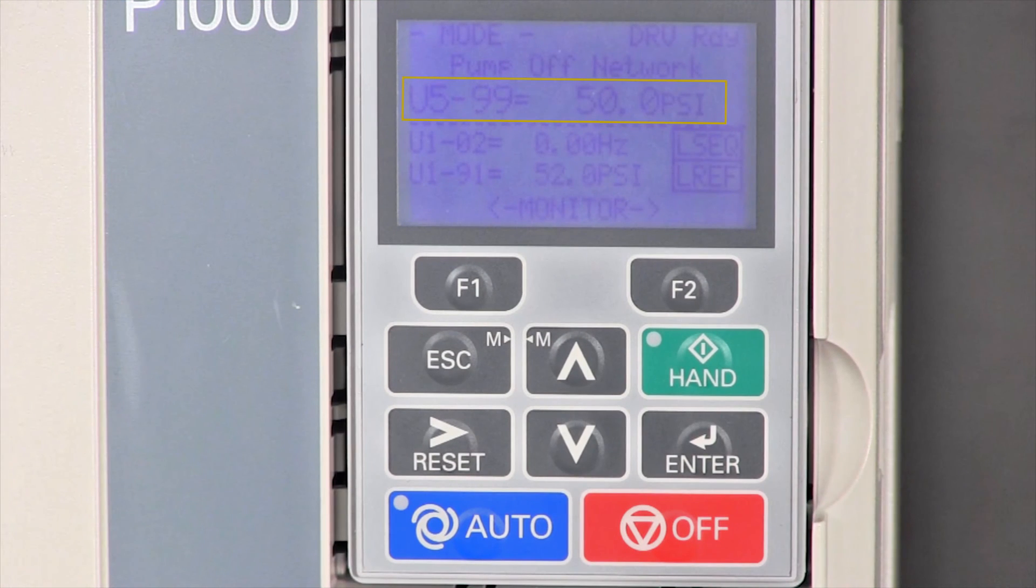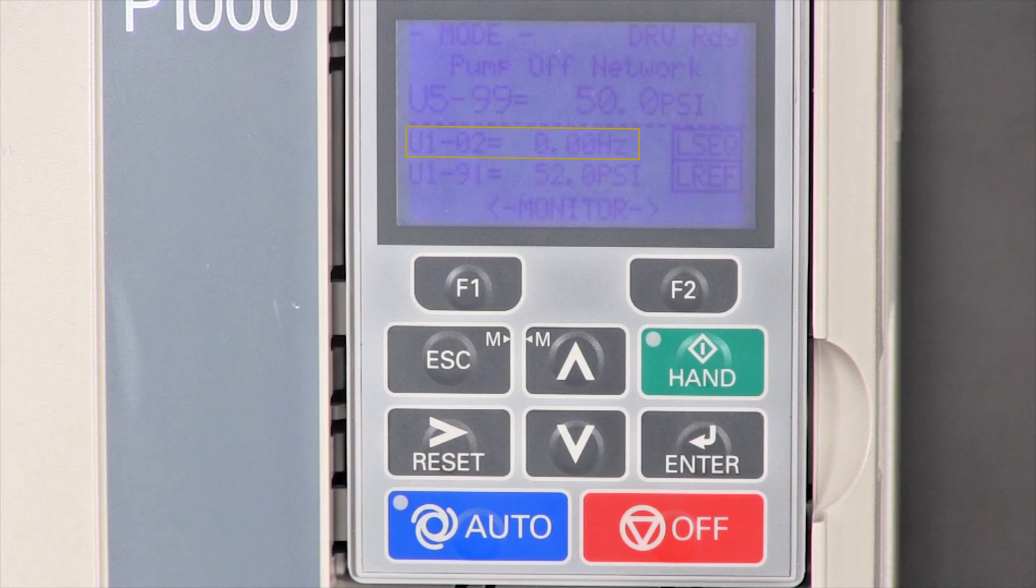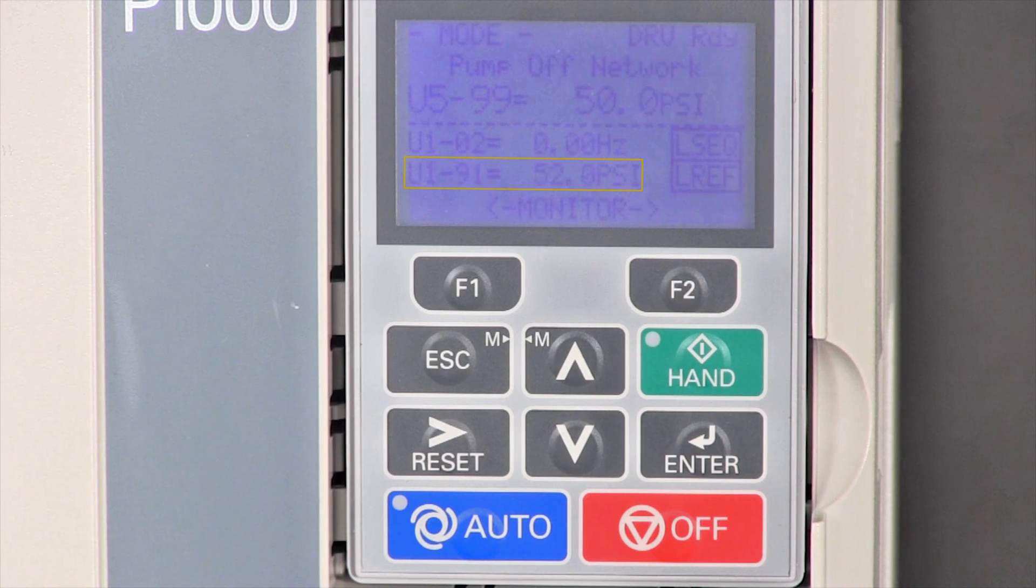The U1-02 output frequency, this is the speed the pump is turning in Hertz. And the U1-91 pressure feedback, this is the actual system pressure as measured by the pressure transducer.